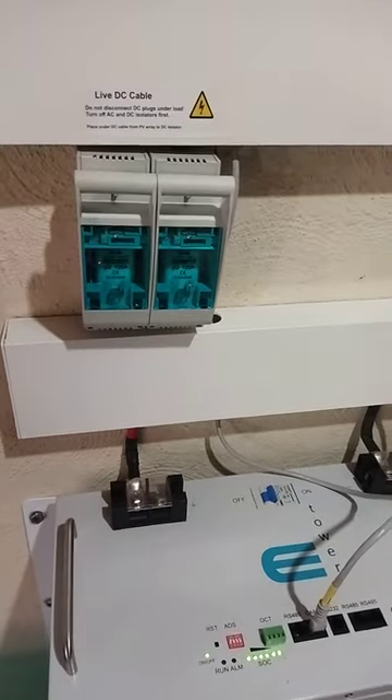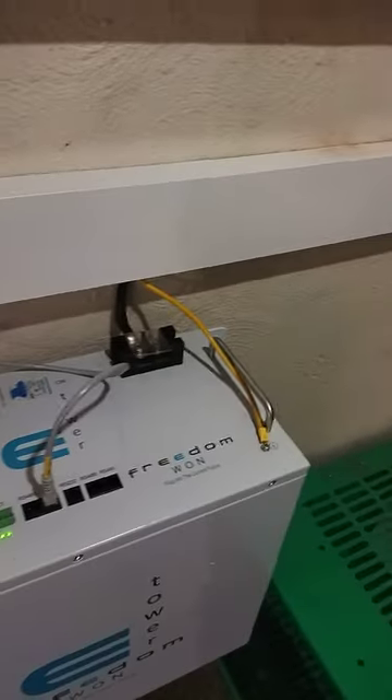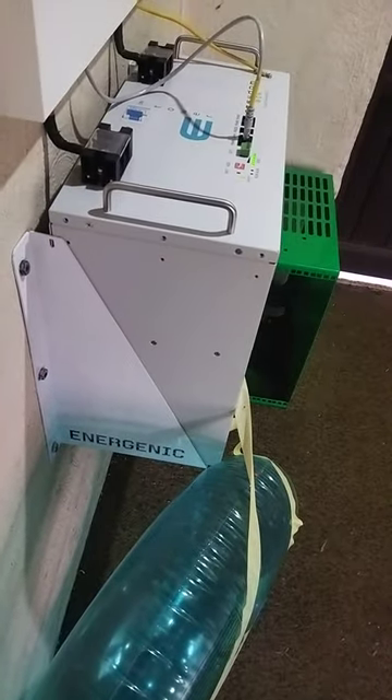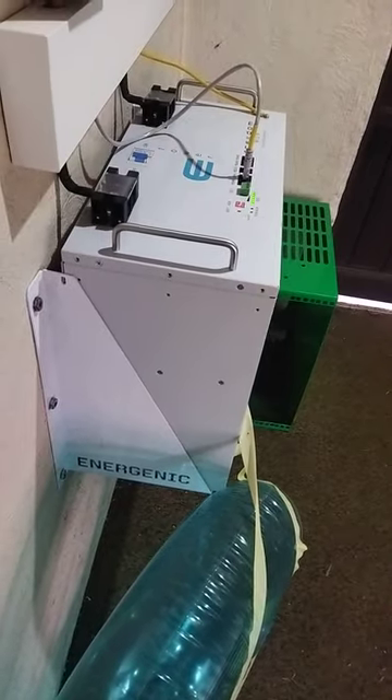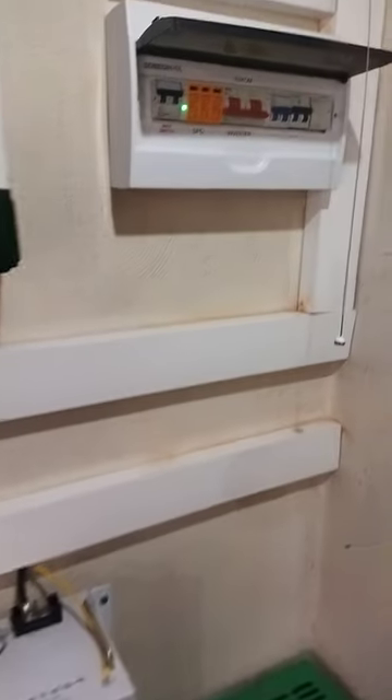We are using a 125 amp fuse holder rated for 160 amp with 125 amp fuses, and 35 millimeter cable that comes with the battery. It also comes with a ready-made bracket from Energenic — they install generators but they also supply a lot of Freedom Won batteries, and they make the frames for the battery to sit on.